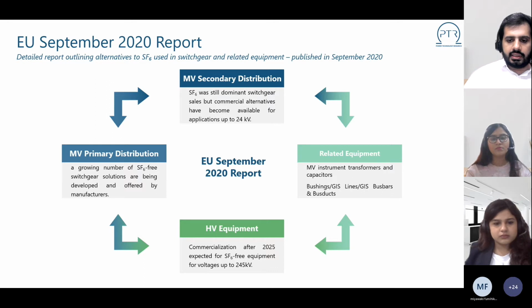Lastly, it was also suggested by the Commission that for medium voltage secondary switchgear, complete replacement be preferred over partial retrofit. For new medium voltage primary distribution switchgear, the Commission found that SF6-free alternatives have always been available and more solutions were being developed. Characteristics like physical dimensions, technical life and reliability were apparently identical to the equivalent solutions of the same manufacturers that use SF6.